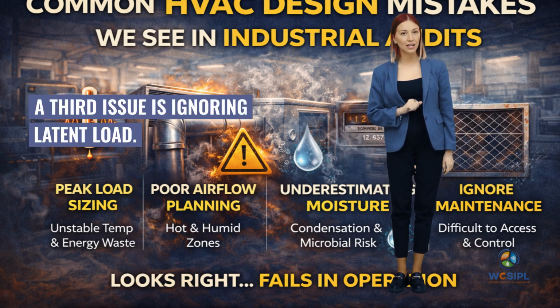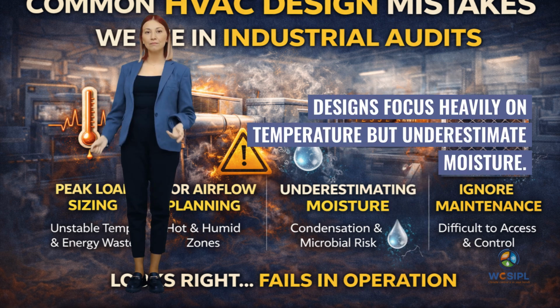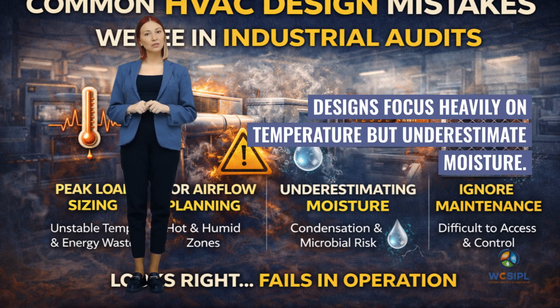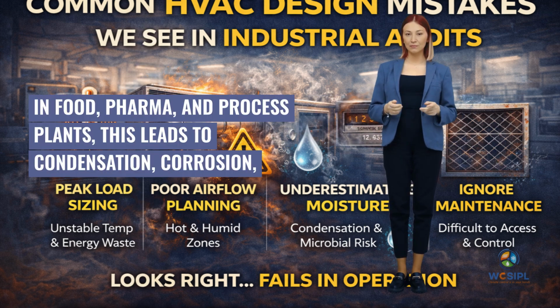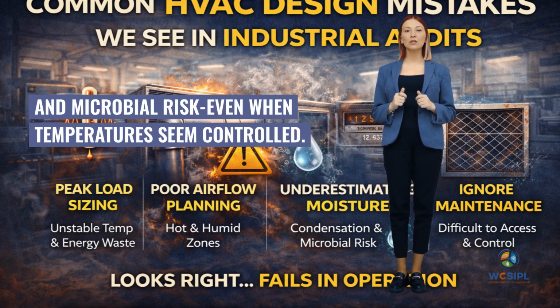A third issue is ignoring latent load. Designs focus heavily on temperature but underestimate moisture. In food, pharma, and process plants, this leads to condensation, corrosion, and microbial risk even when temperatures seem controlled.